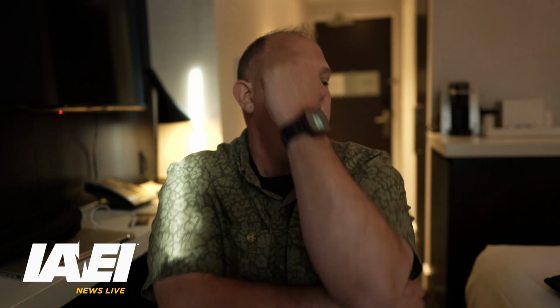And then there was 70-122, which is the last one. This was like a no-brainer. Actually, it wasn't a no-brainer. I'm going to tell you what this was. This one was luminaires with control inputs that provide emergency illumination in 700.24. In B, it says directly controlled luminaire. The language says what they accepted was where emergency illumination is provided by one or more DCLs by disconnection of their control input by a listed ELCD upon loss of normal power, such DCLs shall not be required to be listed for use in emergency systems.